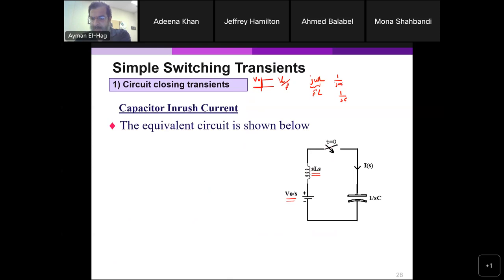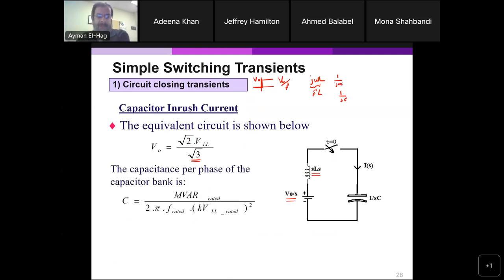So we have a circuit here, we close the switch, and we have a very simple circuit, simple KVL. Now, what is the magnitude of the voltage? We said that we would use the peak value of the single line to ground. So if we have 13.8 kilovolt line to line, divide by root 3 to get the line to neutral, and then multiply by root 2 to change the RMS value to the peak value. You use that peak value as your V0 to get the estimate of the current.